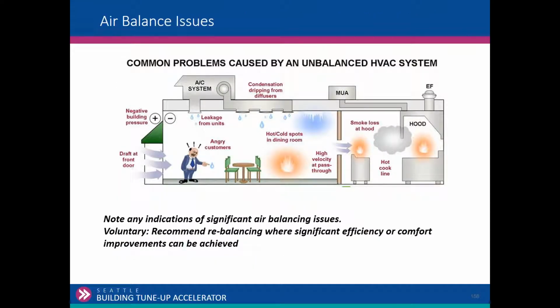Air balance issues. One of the requirements is that you note any indications of significant air balance problems. This is a voluntary thing. We're not requiring you to hire a balancing contractor to go in there and do an air balance. But if there's obvious stuff, you open the door and it's a wind tunnel coming through, or obvious overpressurization or underpressurization, then we want that noted in the report.